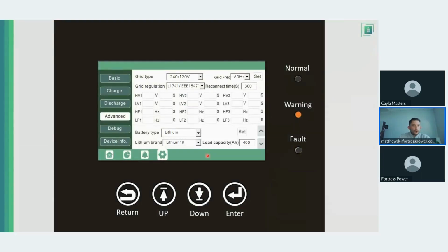Then you're going to set your grid type, your grid regulation, and then on the battery type, you're going to select lithium, and then it's going to say lithium brand 18. Now, typically, this should be coming like this by default, but if you're using another solution, then this would be the way to select your lithium brand.